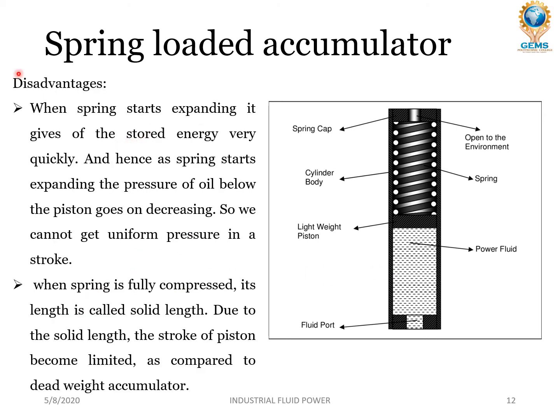The disadvantages of the spring loaded accumulator are: when the spring starts expanding it releases the stored energy very quickly, and as the spring expands the pressure of the oil below the piston goes on decreasing, so we cannot get uniform pressure throughout the stroke. Also, when the spring is fully compressed its length is called the solid length, and due to this solid length the stroke of the piston becomes limited compared to the dead weight accumulator.